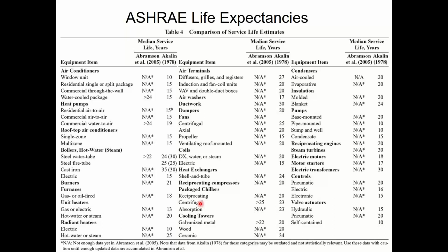For today's purposes, let's look at some of the common things that we'd have for a package system, right? So a typical package system usually means a rooftop system, and we're typically talking about single zone. Average life expectancy is 15 years. That means somebody's going to have one that's 23 years old and it's still working well. And somebody else put theirs in the gutter at year 12 because they beat the hell out of it and didn't maintain it, right? But to give you a check figure, it's about 15 years. So if your system's around that age, that's going to affect my decisions.